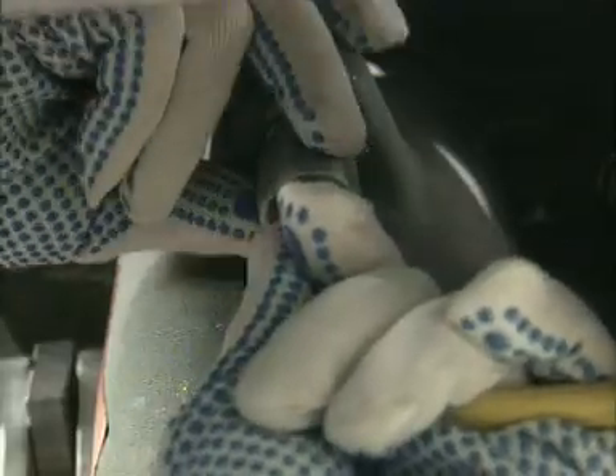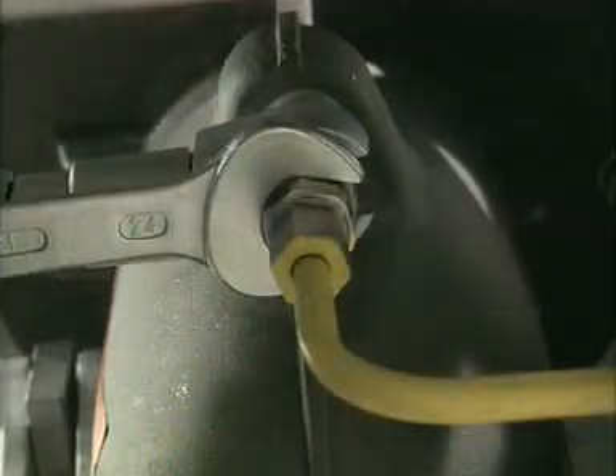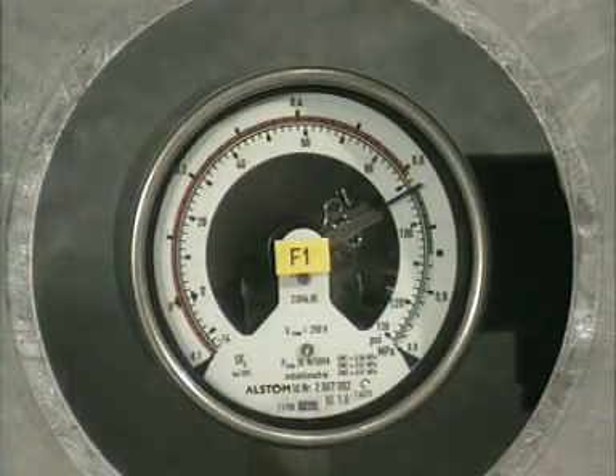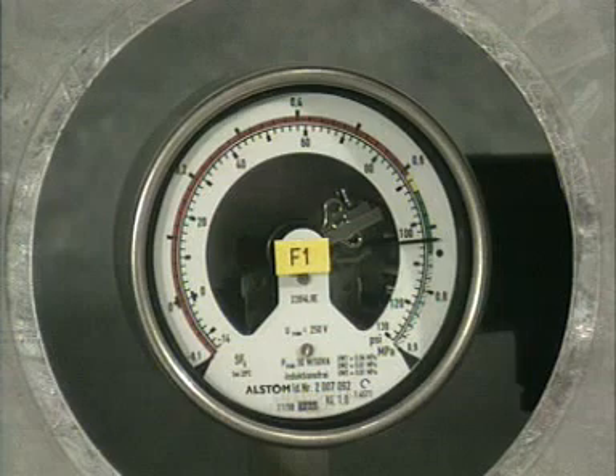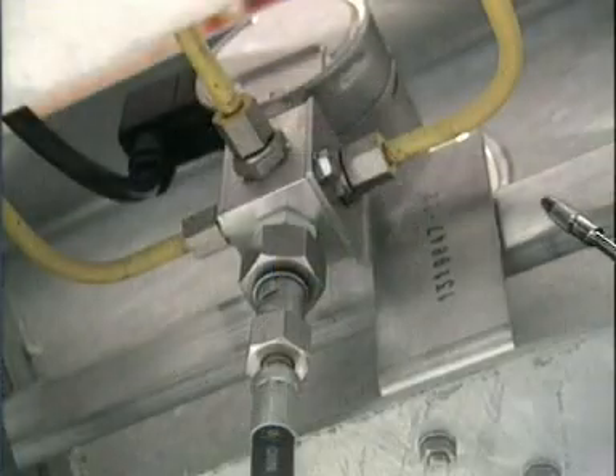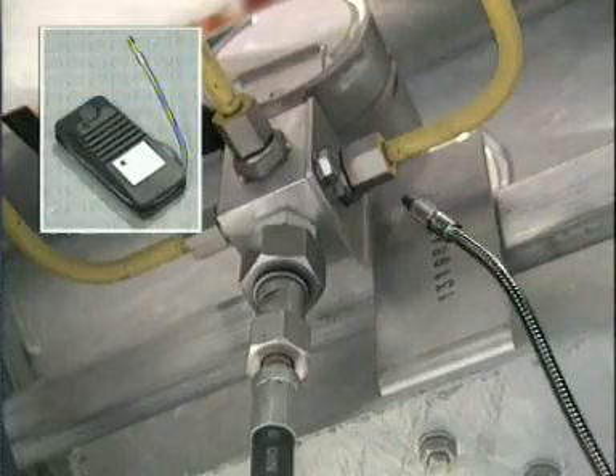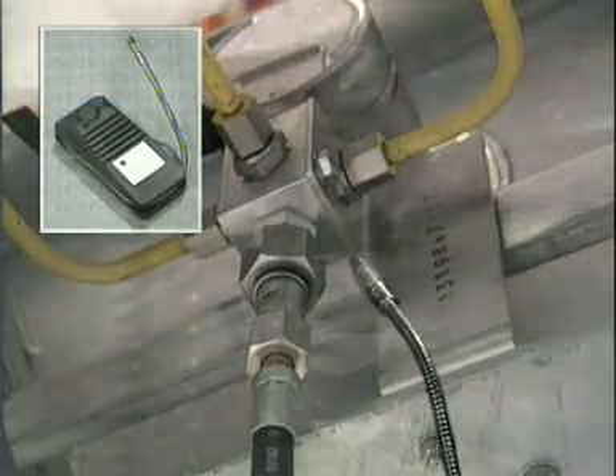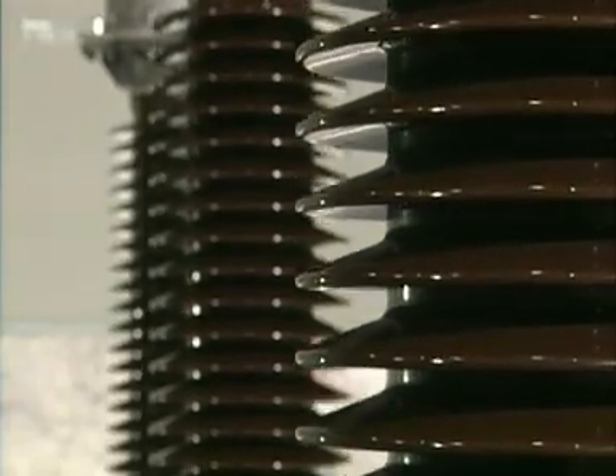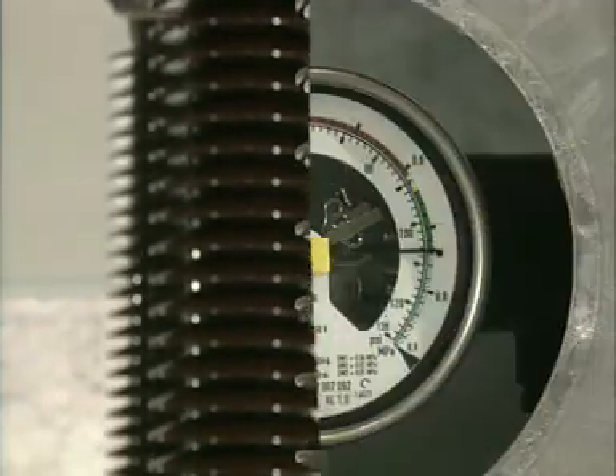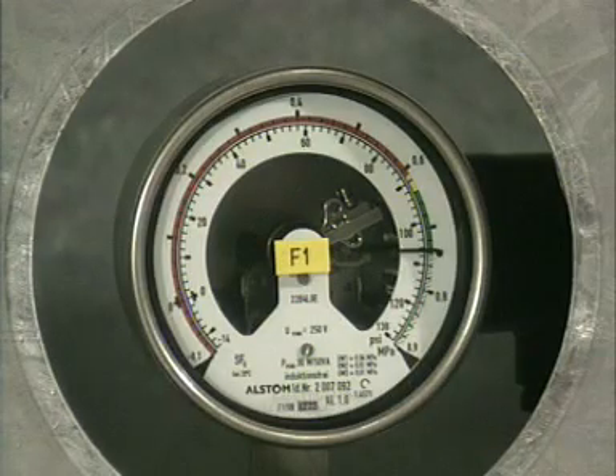Before filling the breaker with gas, connect the SF6 piping system to all 3 pole columns and tighten using a torque wrench. Fill up the breaker to the rated pressure marking in the green scale range of the density monitor. Check all sealing points for leak tightness using an SF6 leak detector. After a temperature equalization period of approximately 1 hour, check the SF6 pressure again and correct it if necessary.